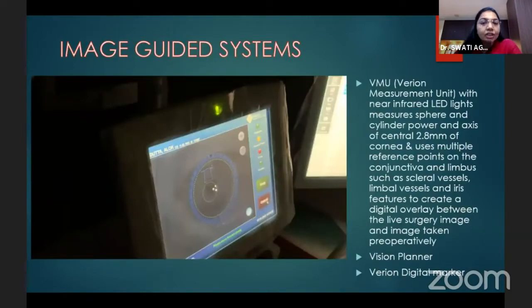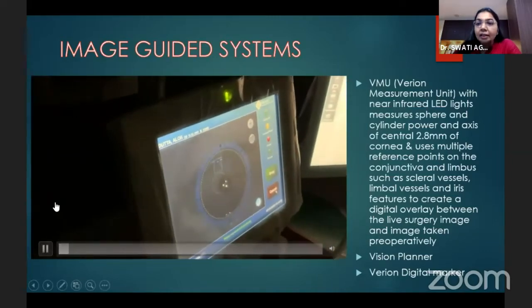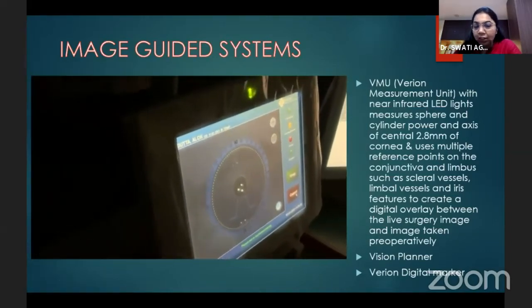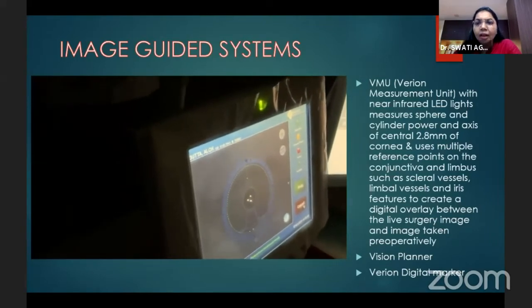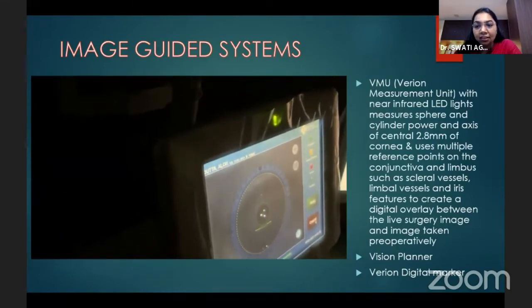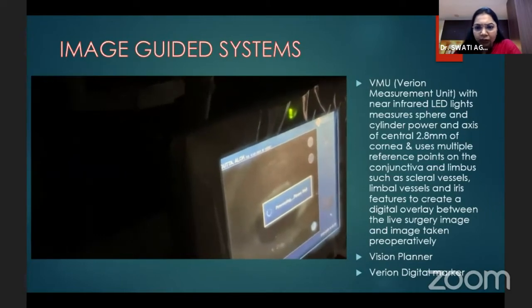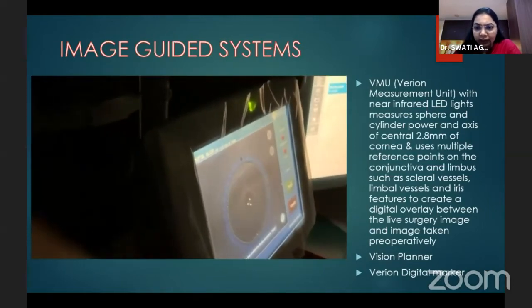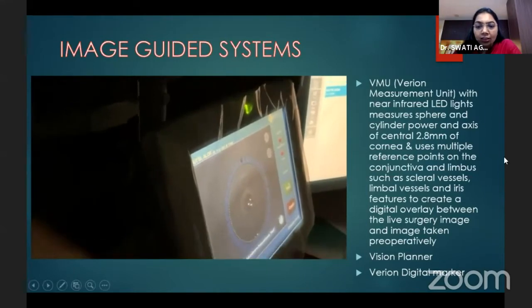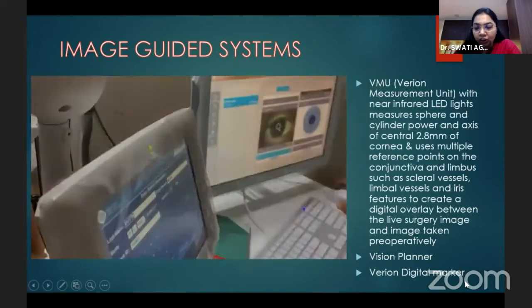For a good surgical flow, image-guided systems have become very common. The image-guided system consists of three units. The Verion measurement unit — it can be Verion, Callisto, or others — uses near-infrared LED lights to measure the sphere and cylinder of the central 2.8mm of the cornea, and uses multiple reference points on the conjunctiva, limbus, and scleral vessels. This detail is then passed to the vision planner and into the Verion digital marker.